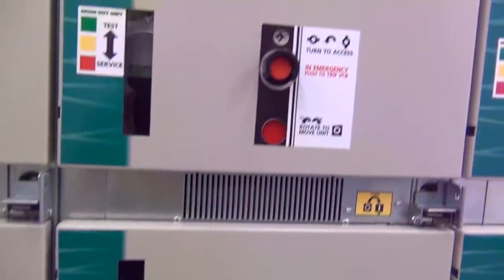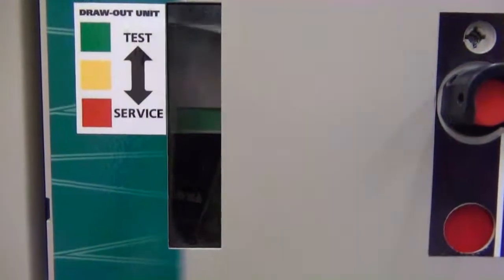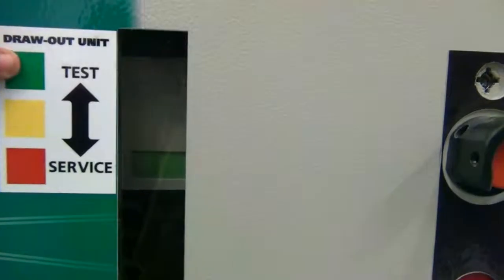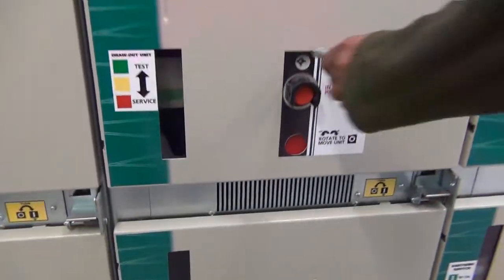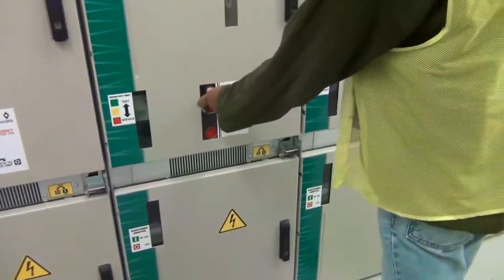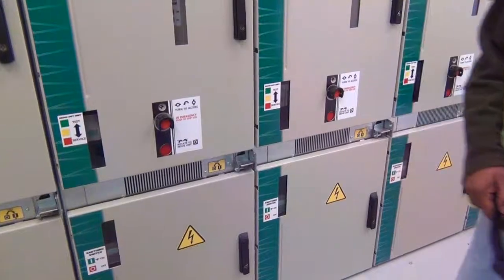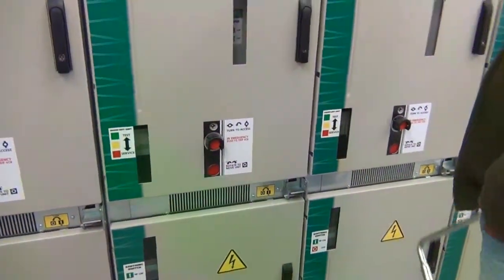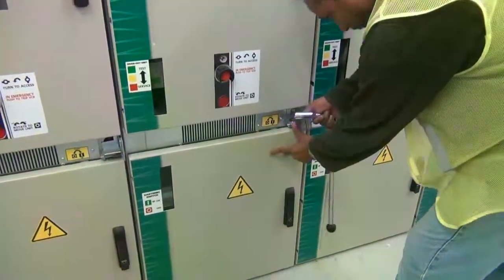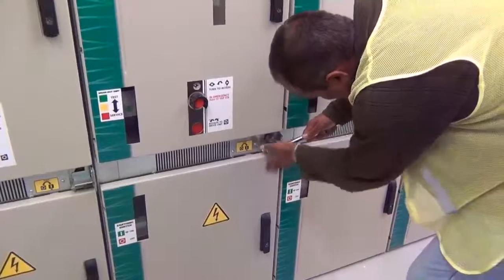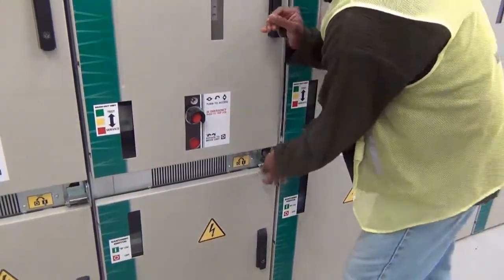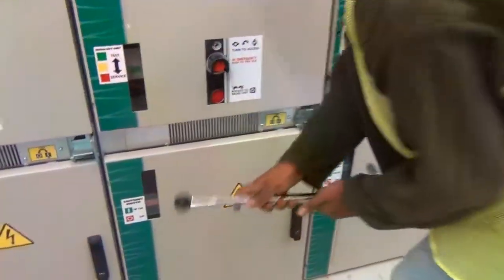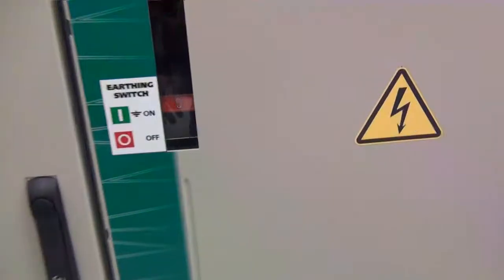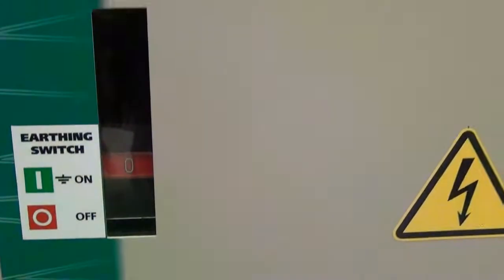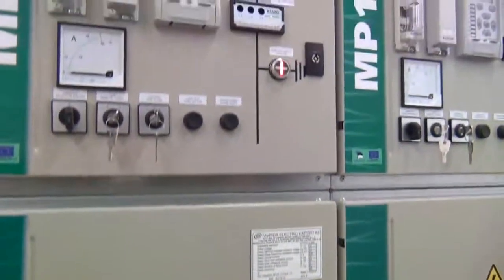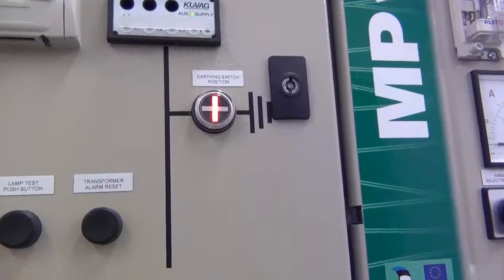Now to rack in the breaker, as you can see, the condition of the breaker is green, which means it is in test condition. So now the first thing is the earth switch will be put in off condition. The earthing switch will now be put off. Now two things happen. One is the earth switch is obviously now off, can be clearly seen, and also if you go up, you will see that the earth switch is now in off condition.